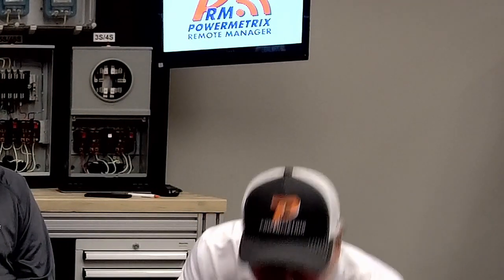I'm going to test that meter with the primary conductors, like a flex core, around the primaries. And that's the current I'm going to read to do that meter test. So the only other thing I have to do is say my K sub H of a 9S meter is now not 1.8, because I'm looking at the primary current instead of the secondary current. So I have to take the CT ratio into account for that.